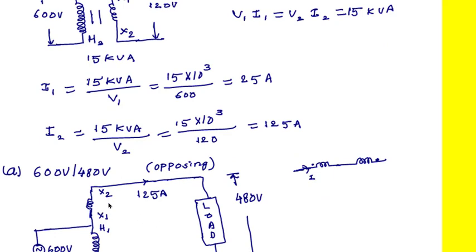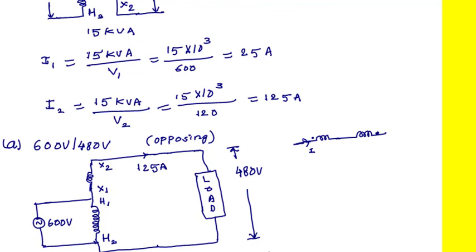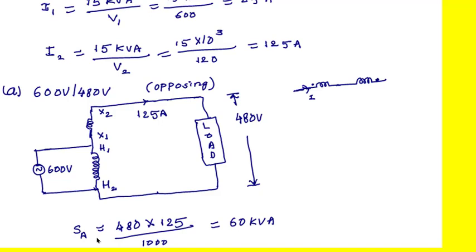The LV winding current capacity is 125 amperes, so that current can flow here. The load voltage is 480 volts as given. We know the load current and load voltage, so the kVA rating of this auto transformer is SA = 480 × 125 ÷ 1000 = 60 kVA.